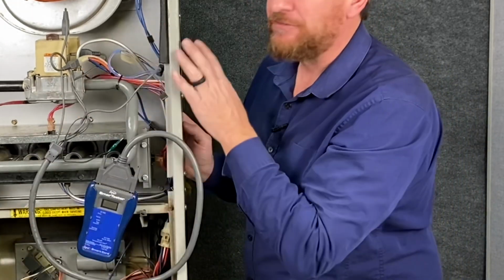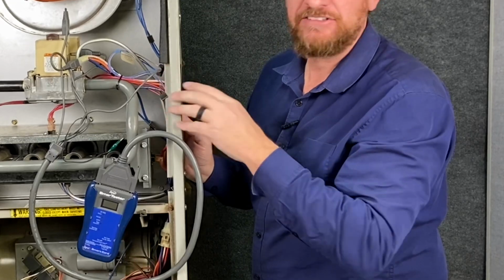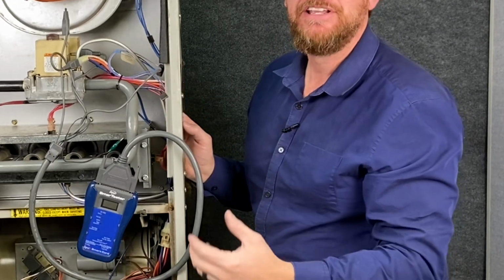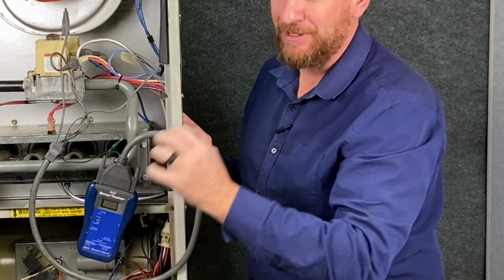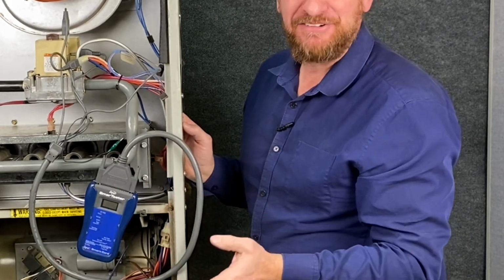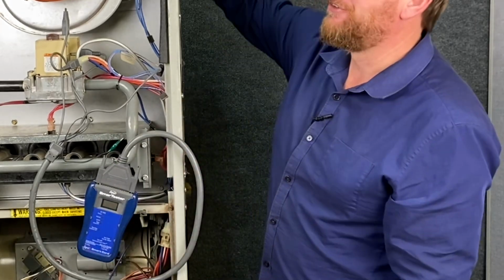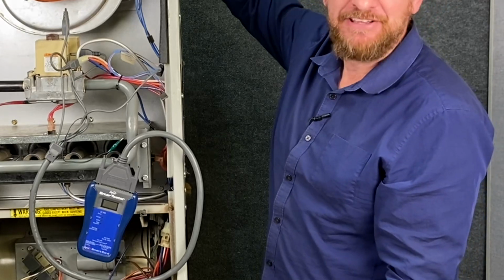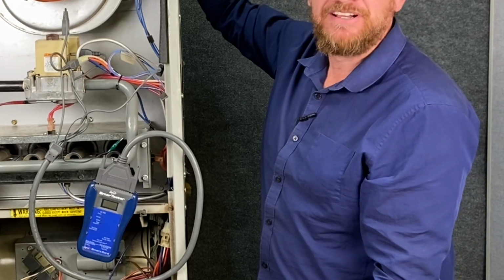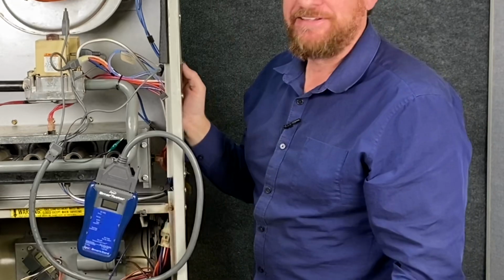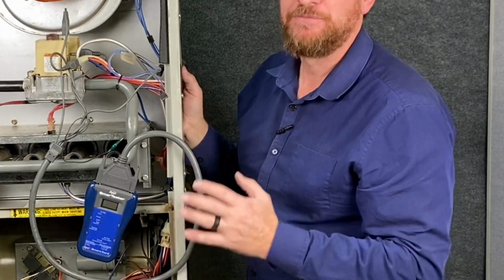furnace. Now this furnace is designed for natural gas. I do not have any gas here at this building, so I have it modified on propane, so it will not run right. It's actually dangerous to do. Don't run it at home. Also, I don't have my flue pipe hooked up. I have a big vent fan set up to get the carbon monoxide out of the way, but that's also quite dangerous.